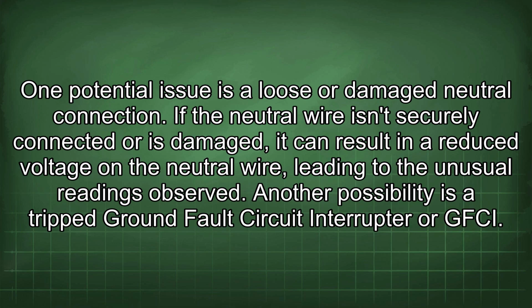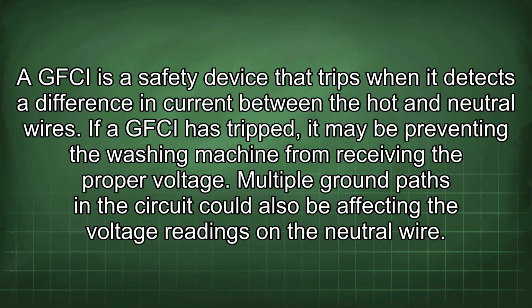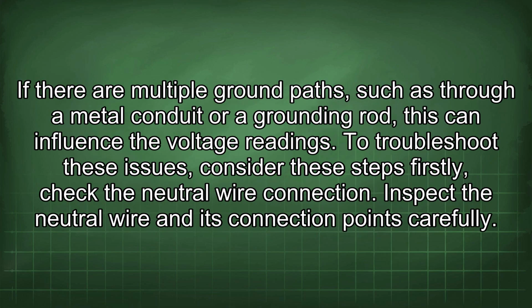Another possibility is a tripped ground fault circuit interrupter, or GFCI. A GFCI is a safety device that trips when it detects a difference in current between the hot and neutral wires. If a GFCI has tripped, it may be preventing the washing machine from receiving the proper voltage. Multiple ground paths in the circuit could also be affecting the voltage readings in the neutral wire. If there are multiple ground paths, such as through a metal conduit or a grounding rod, this can influence the voltage readings. To troubleshoot these issues, consider these steps.